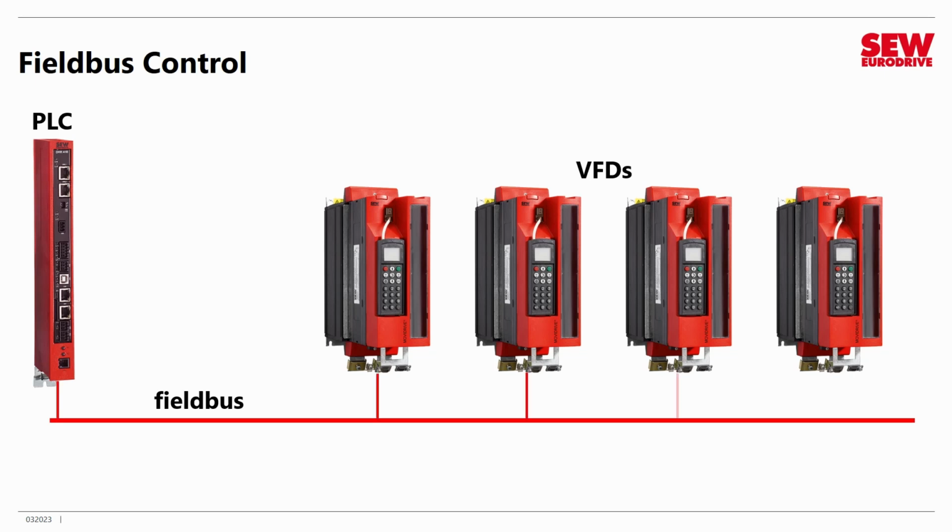It will connect the PLC to all the VFDs, and the PLC can then send commands to the VFDs to make them do interesting things, and the VFDs can report their status back to the PLC. And of course, since you've learned IPOS, this gets much more powerful since you can have IPOS programs running in the VFDs doing very sophisticated communication and control tasks and then passing information back to the PLC.